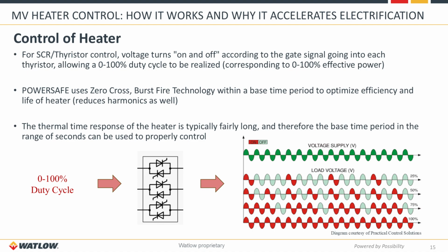With an SCR or thyristor, you can basically manipulate that voltage, how often it turns on, how often it turns off within a period of time, effectively creating a duty cycle between 0 and 100% during that base time period. Watlow uses a zero-cross burst firing technology within its system to ensure that we are providing adequate voltage with less harmonics and also keeping the element temperature of the heater constant over time. We do this, like I said, by using the zero-cross burst fire technology. There's a diagram in the lower side of the presentation slide here that shows you this.